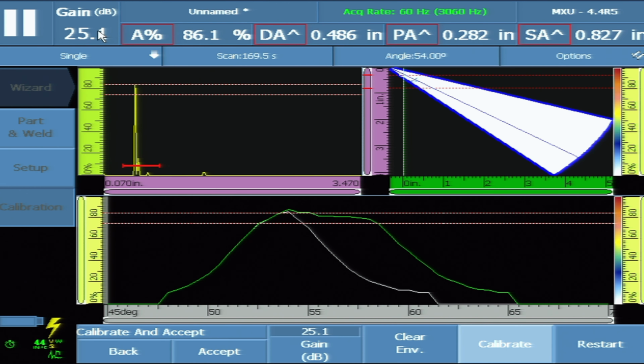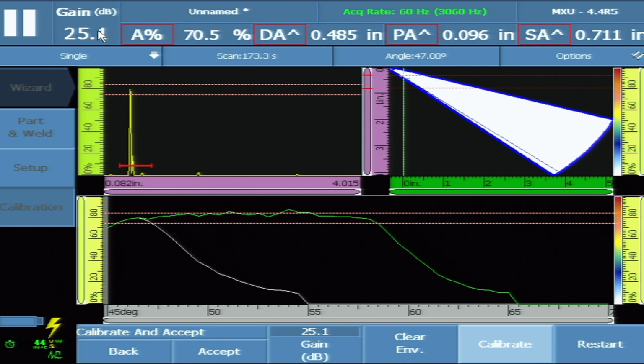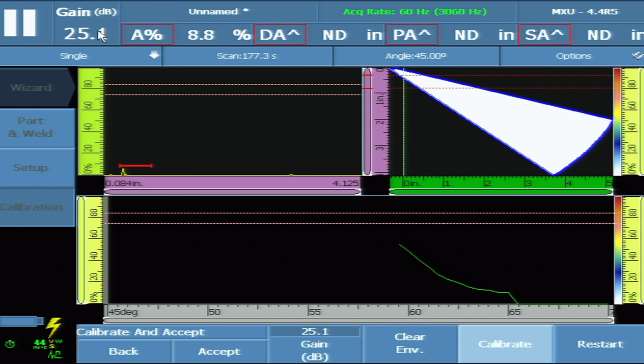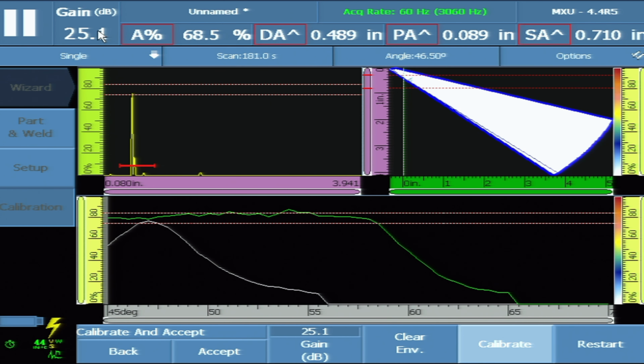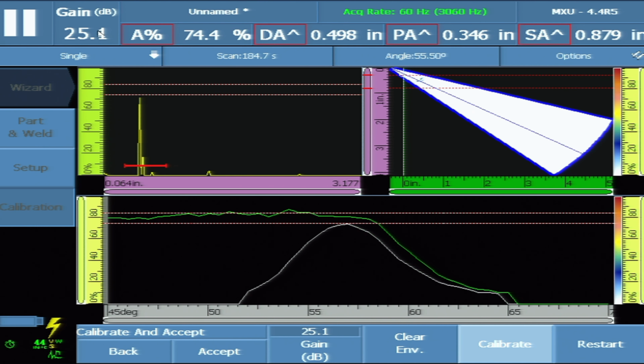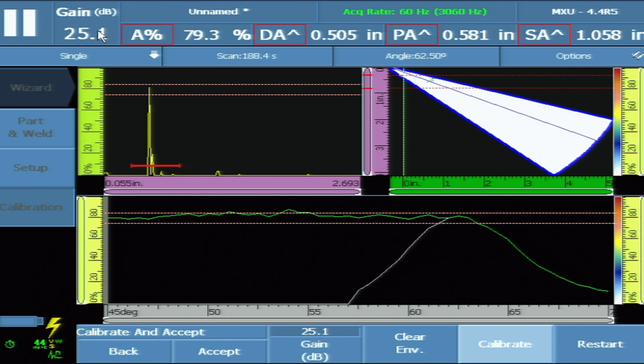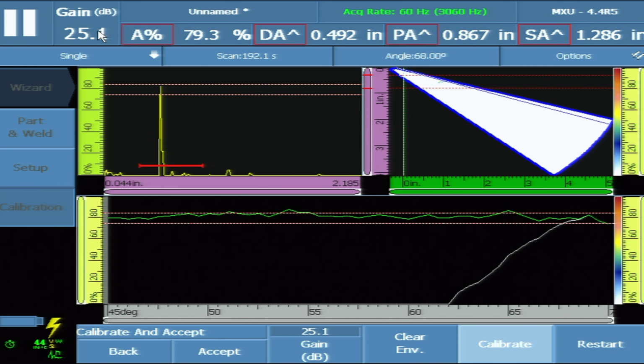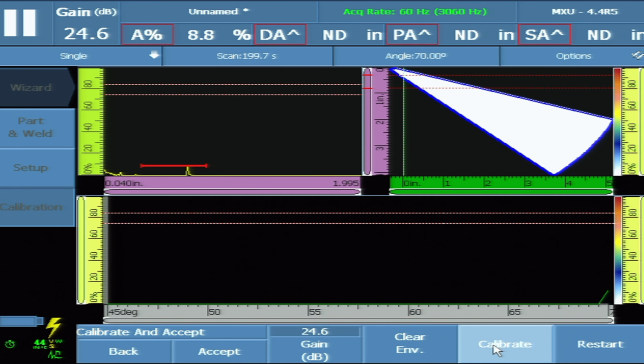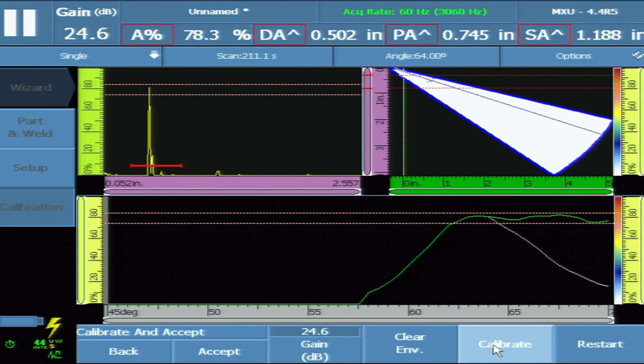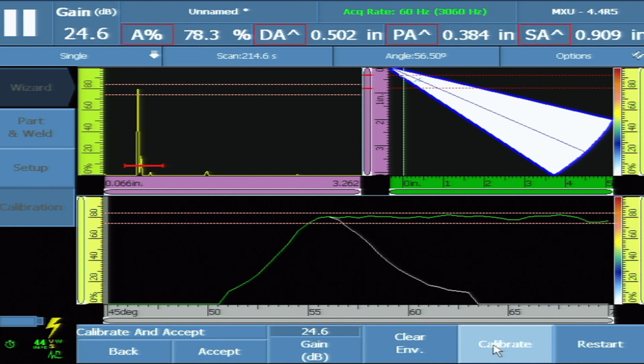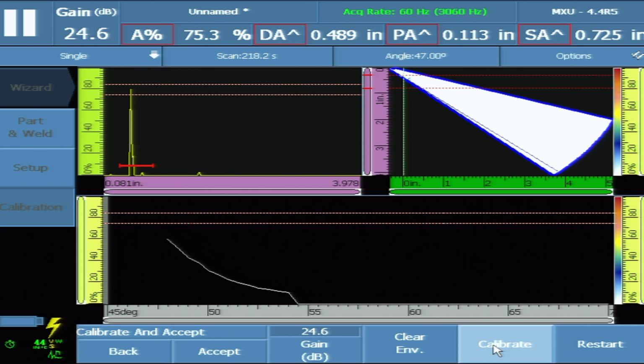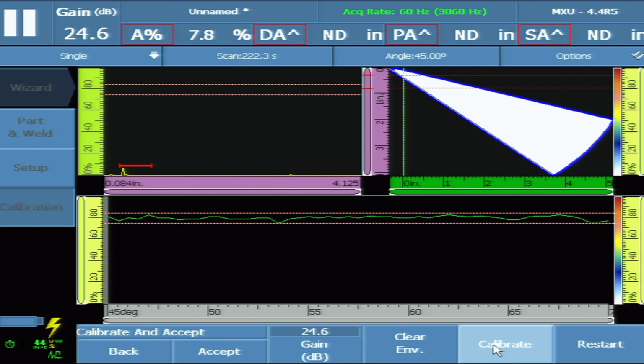Now we're going to walk it through all of these angles, keeping it in that red line. We're a little bit out on that one. But we're going to go all the way through. We're out on another one. All right. We're going to calibrate one more time. And it's going to take some gain out. Now you walk through all your angles. And they're all going to be within that red dotted line. And we're going to walk right through the 45 and hit accept.